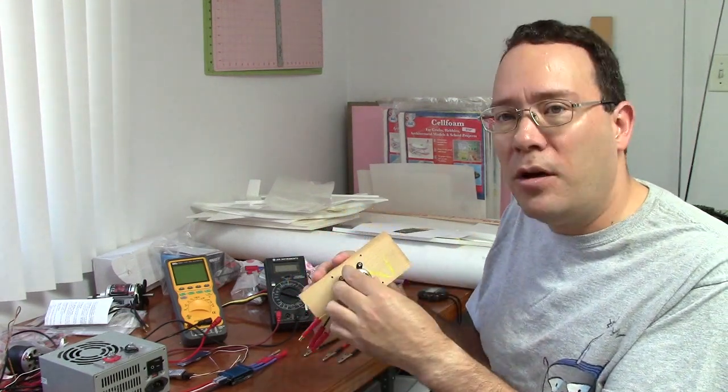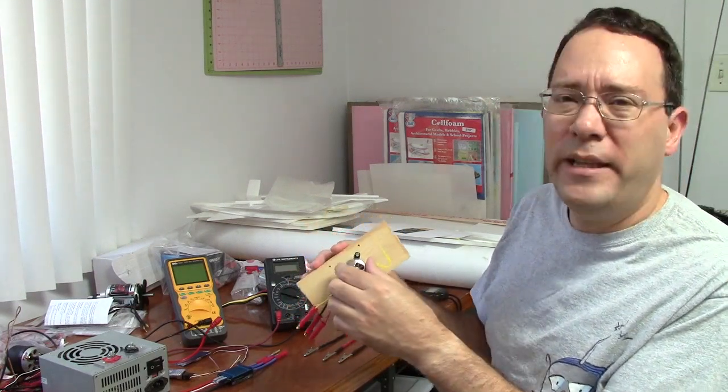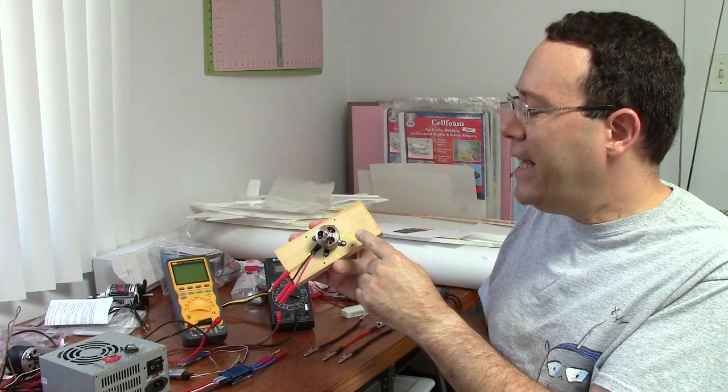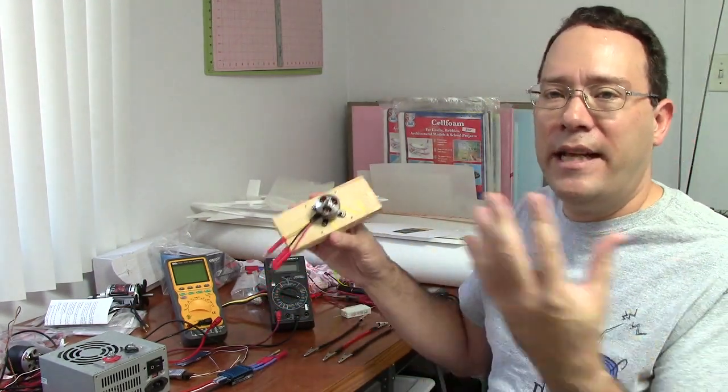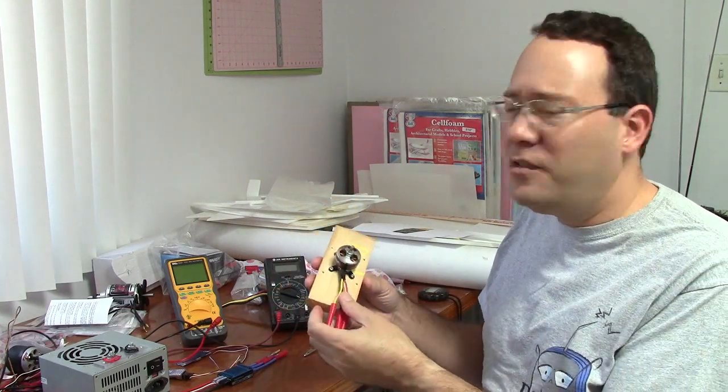first of all, varies by the motor. I think the smaller motors have more delays. But the power factor varies also with the speed of the motor. So even if you take an accurate measurement, the motor then runs at a different speed. The power factor could be something else entirely different. So it's very troublesome.